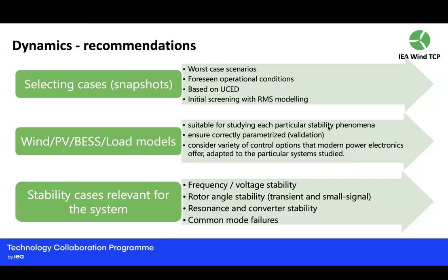Inertia is the simplest of them all, because you can say system wide, or maybe system pocket wide. But say you have a voltage stability constraint, how do you translate that into a more simple constraint? Maybe you have a certain combination of resources that you cannot allow to operate together, or you need to change the control parameters on the fly. So then that becomes more complicated.